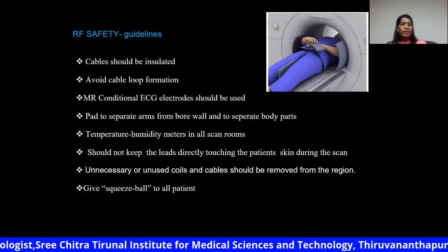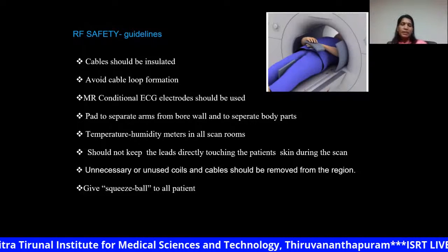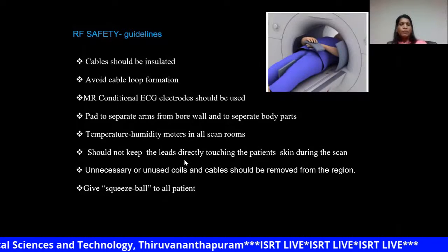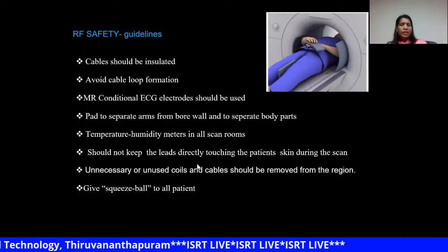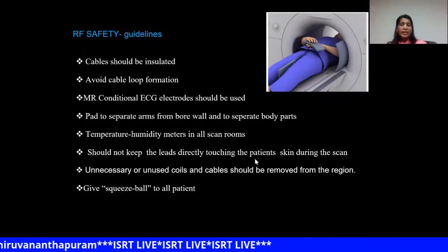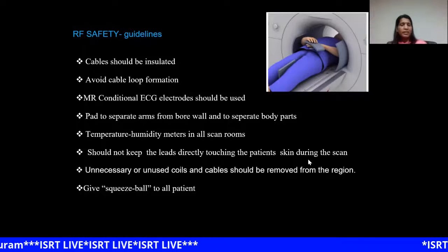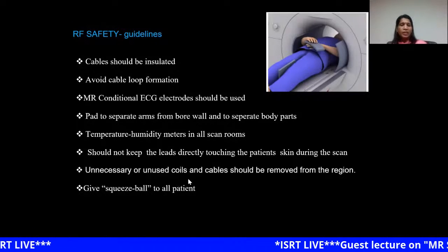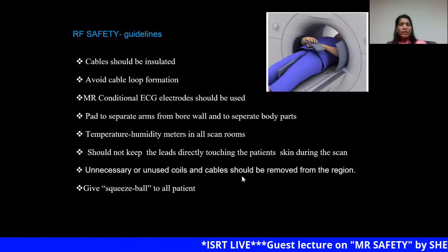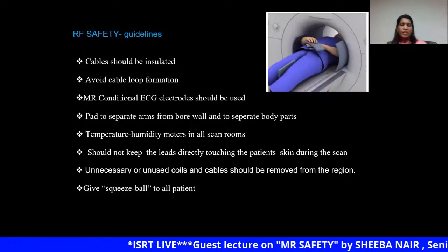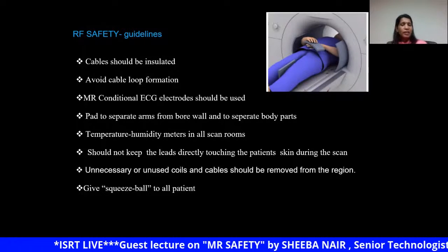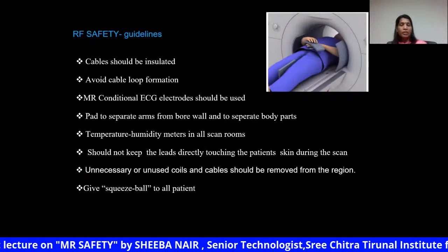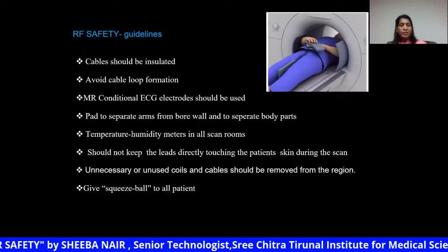RF pads. And there should be temperature and humidity meters in the MR scanner room. Also, avoid the leads or any other monitoring device touching the patient's skin directly. And if you are not using any coils or cables, don't keep them in the region of interest.